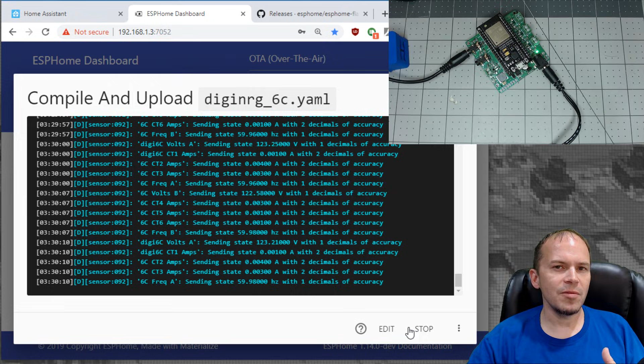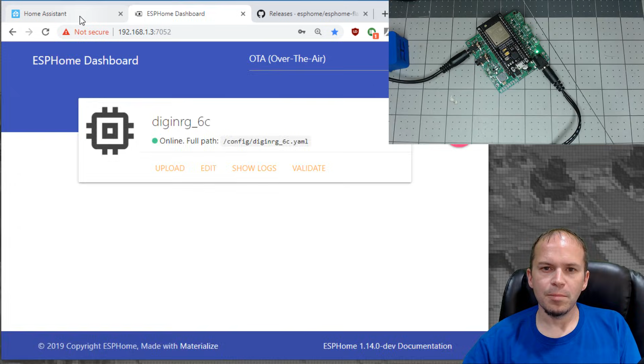So at this point, you could go in and do the integration part if you're using the API, or just go ahead with MQTT in the unused entities and find your sensors that are now posted from this chip. So there we have it. You can see inside of our unused entities, we do have the 6 CT amps along with the frequency for each side, each chip, along with the voltage. So now we need to do a calibration to get our clamp on par.